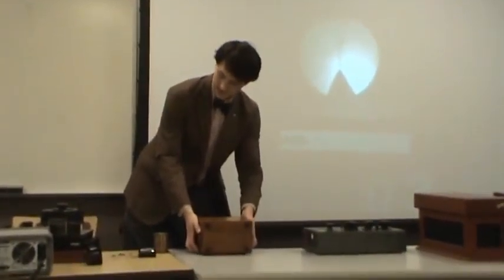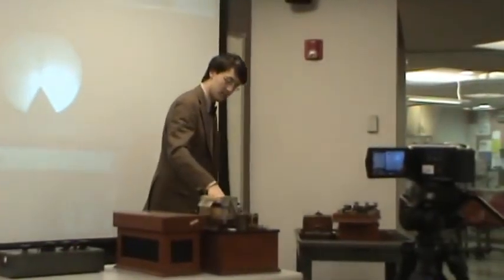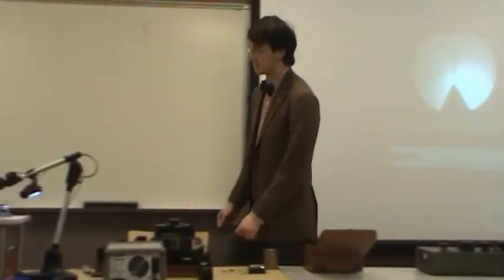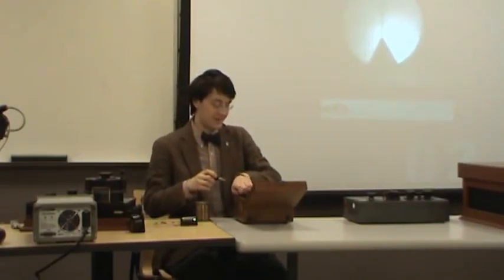This bridge, this Wheatstone bridge, also features large contacts inside. All of the resistors that you see in here typically look like wax-based things. They are manganin spools on ceramic forms with beeswax on them. The beeswax does two things. It keeps moisture out, and it's an indicator to whoever is performing the service on the instrument that you just blew up that you put too much current through the resistor. So we've been doing that kind of indication for a long time.